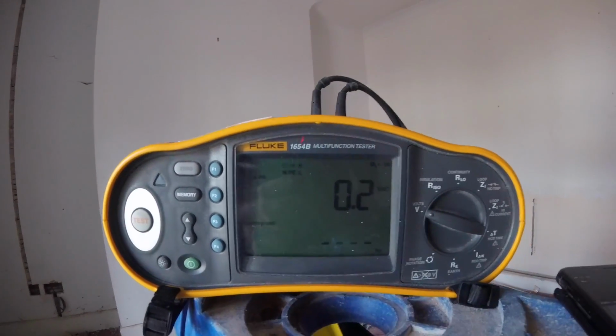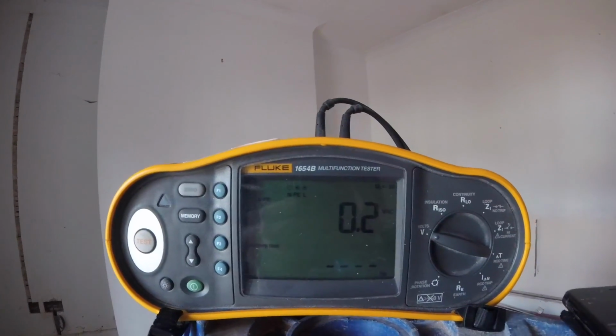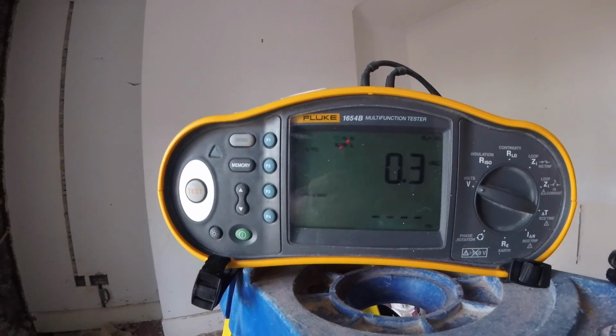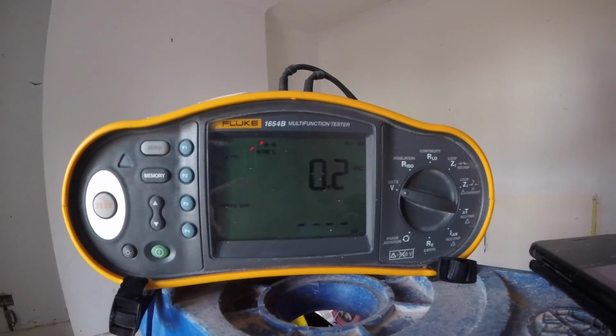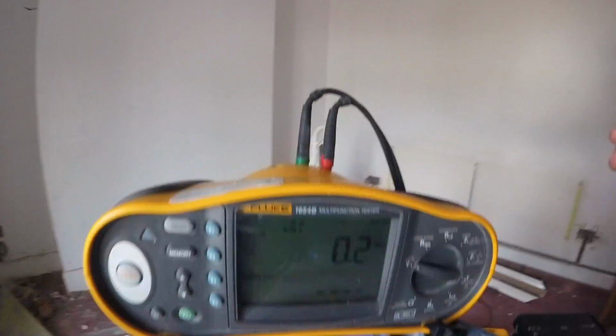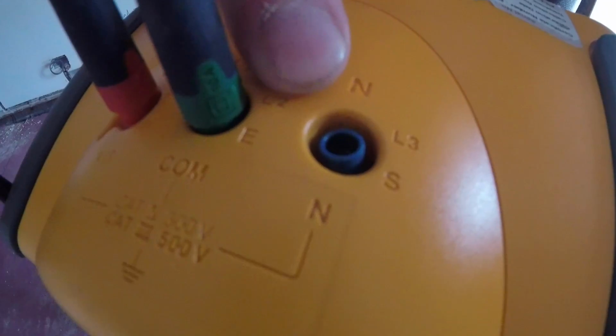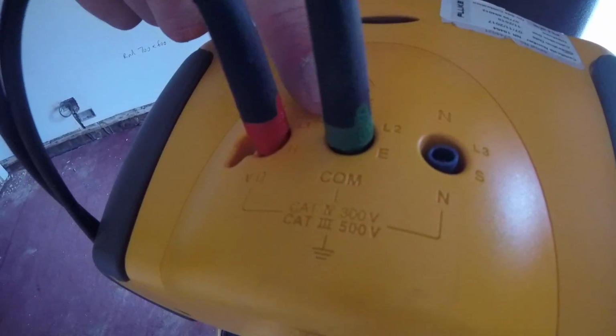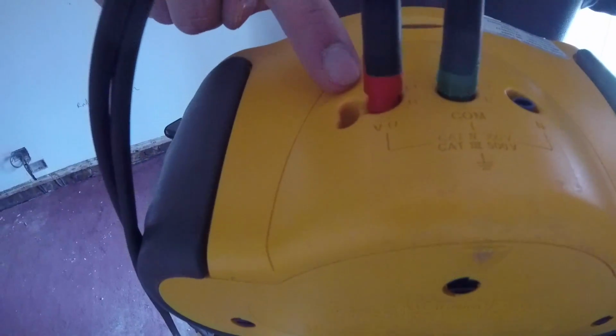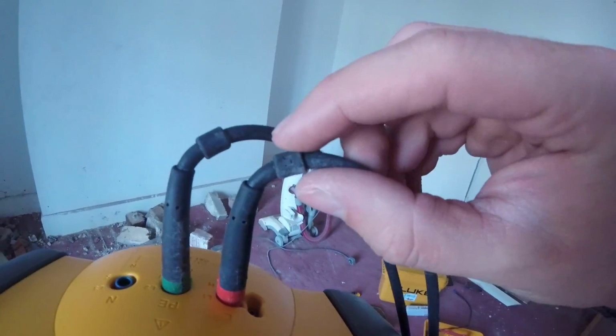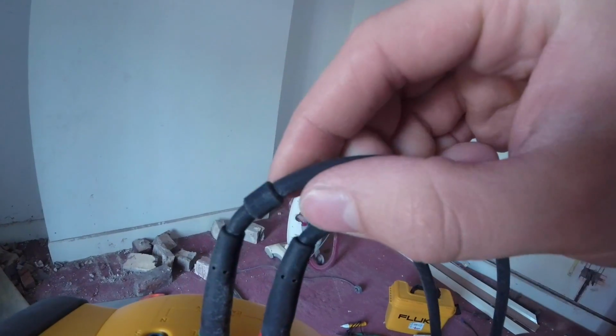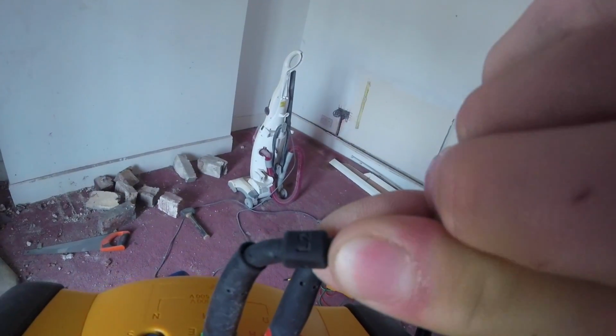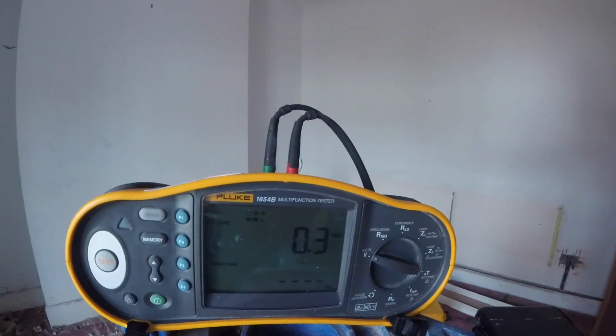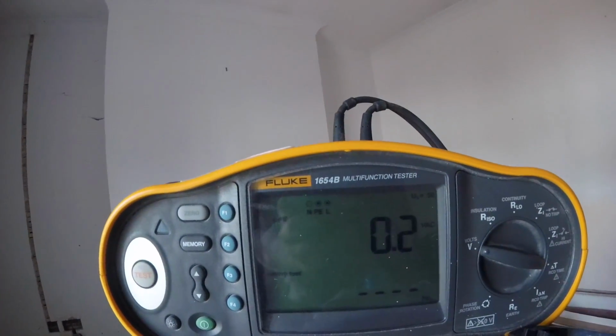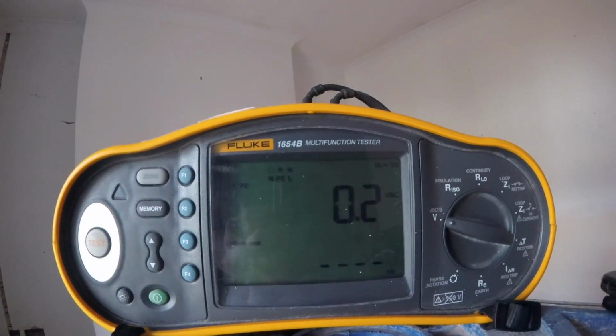So I'm just going to run you through each of the tests. The first setting I've got it on is the voltage. Obviously this measures the voltage wherever you're probed onto, basically. At the moment I've got two probes stuck in the back. They're all colour coded. So that one's the neutral probe, obviously, because it's blue. We've got the PE, which is the earth, and the L, which is the red, live. Each one is also marked with L1, L2, I don't know how well you can see that, for when you're doing your phase rotation tests. All you would do with these probes is stick on live and earth, and that'll come up with your voltage, and that's about it really.